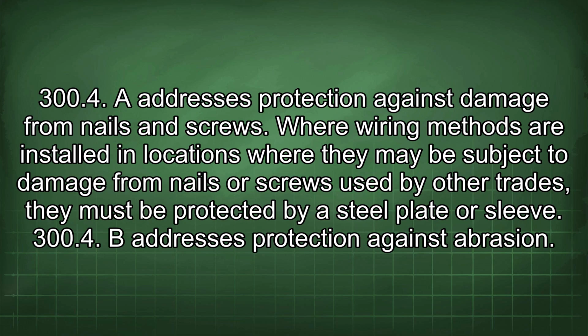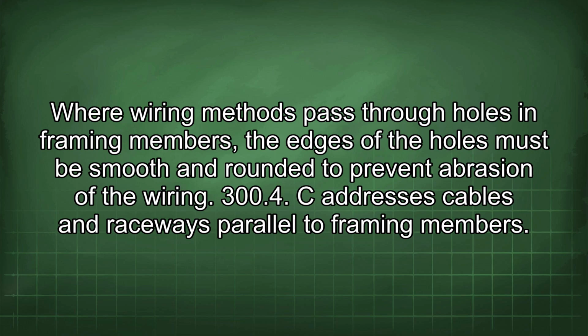300.4 A addresses protection against damage from nails and screws. Where wiring methods are installed in locations where they may be subject to damage from nails or screws used by other trades, they must be protected by a steel plate or sleeve. 300.4 B addresses protection against abrasion. Where wiring methods pass through holes in framing members, the edges of the holes must be smooth and rounded to prevent abrasion of the wiring.